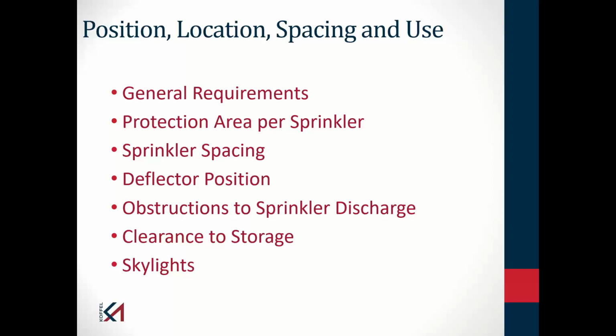In addition to obstructions, we need to get the water over top of the storage. The number you will typically hear is 18 inches. That is a horizontal plane beneath the deflector of the sprinkler. I emphasize that because back in earlier years of my career, when I was with the State Fire Marshal's office, I told a facility that they need to keep the storage 18 inches away from the sprinkler. And they took me at my word. They created a hemisphere with a radius of 18 inches. And 20 inches away from that sprinkler, stuff was stored up to the ceiling.